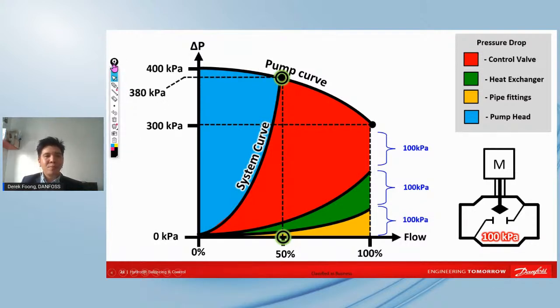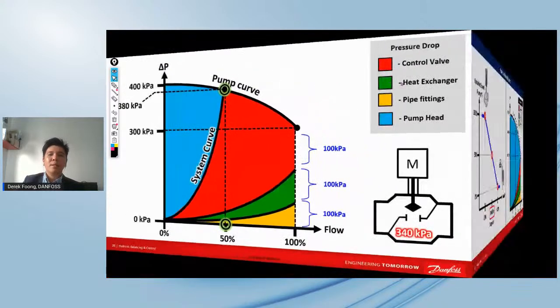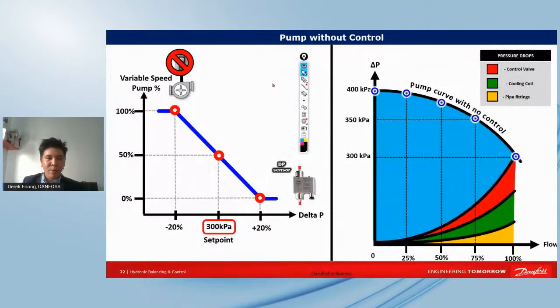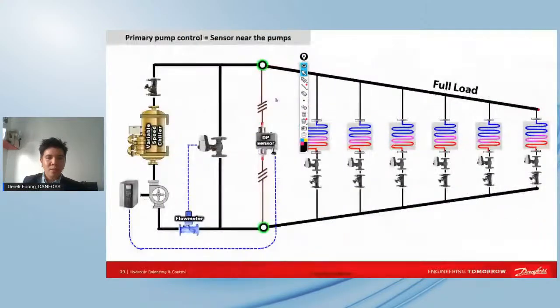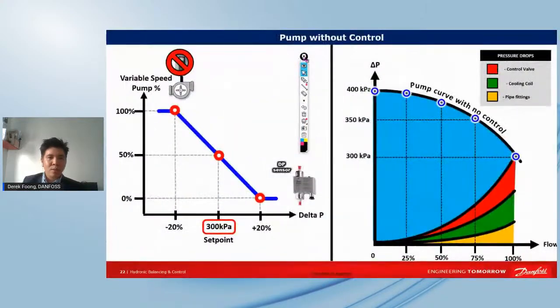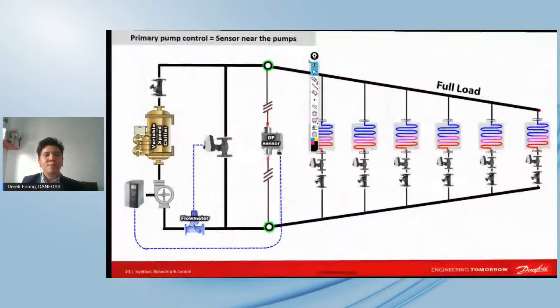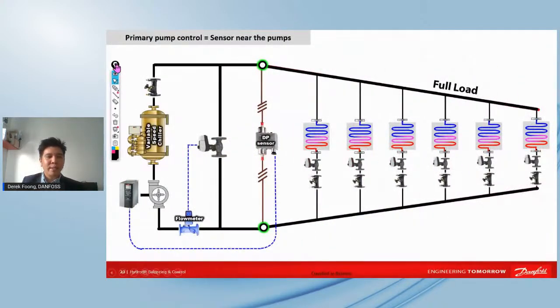All right, so of course pressure builds up when the control valve closes. And then we'll have a lot of hydraulic interactivity in the system. So one valve closing influences the rest of the valves' performance in the system. This one I won't elaborate more because we have covered it just now. No control, sorry, no control means that pressure would build up. Okay, so now let's simulate another point.